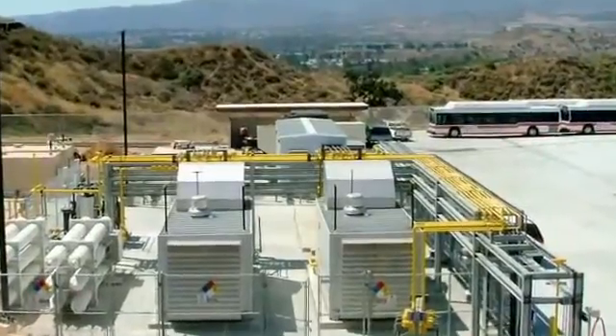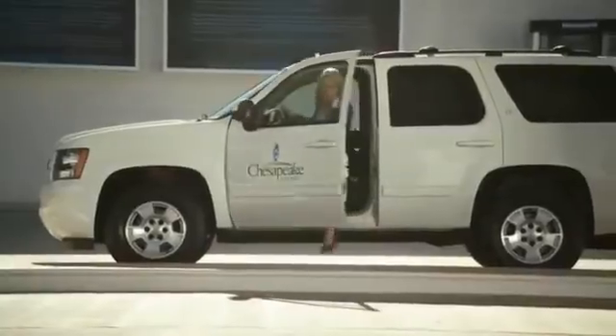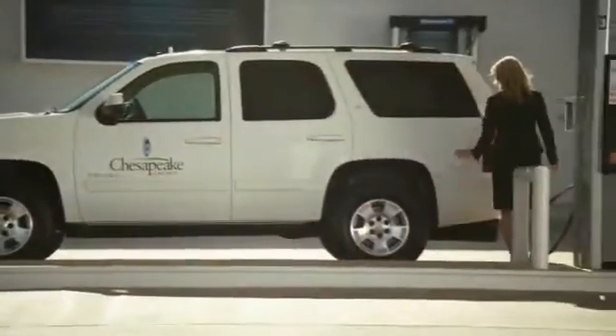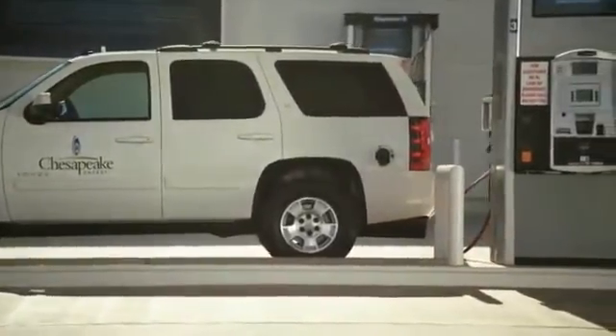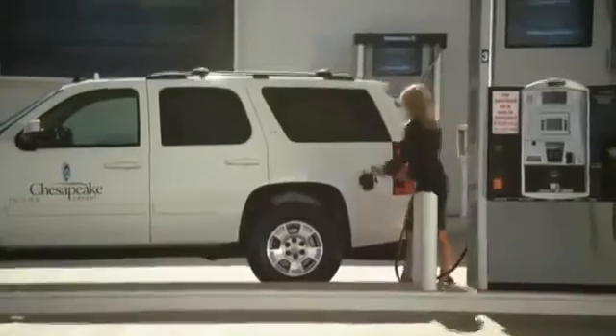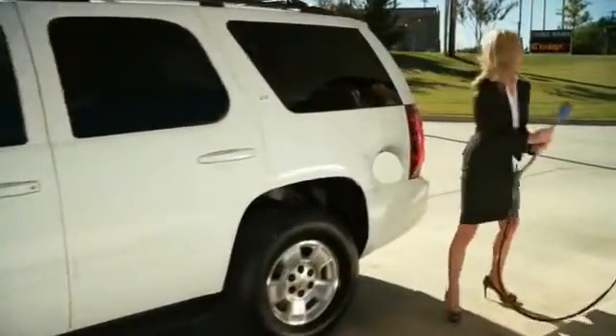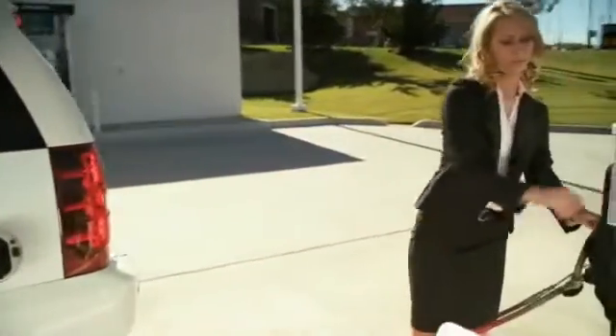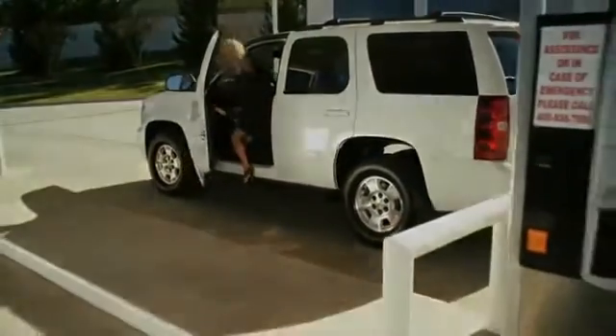If you have gas and electricity and roughly a 30 by 40 foot footprint available, then you can pretty easily site the compressed natural gas fueling equipment. And if you've already got fueling spaces — if you're a public fueling station selling gasoline and diesel — the compressed natural gas dispenser can go in the same area as the liquid fuels, subject to local codes.